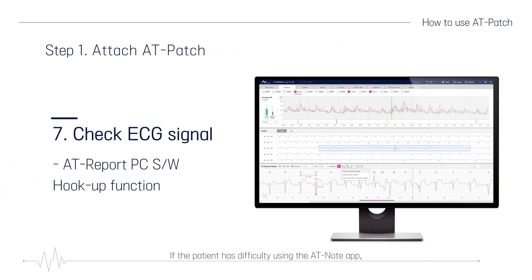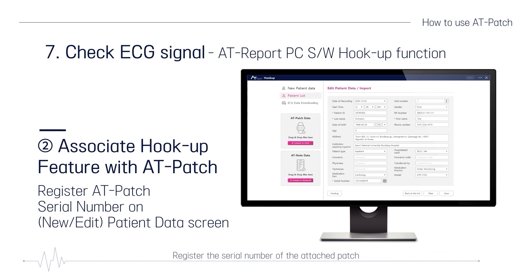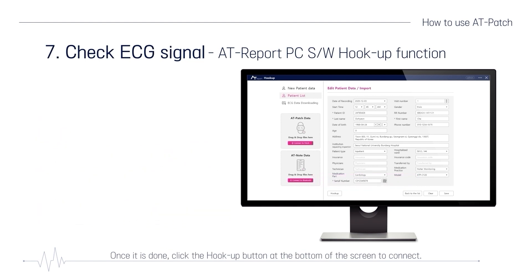If the patient has difficulty using the AT-Note app, use the hookup function of the AT-Report software installed on the PC of a hospital or an affiliated analysis institute. To receive the ECG signals from the patch attached to the patient's chest, connect a Bluetooth dongle to the PC with AT-Report software. Register the serial number of the attached patch on the New/Edit Patient Data screen of the AT-Report software.